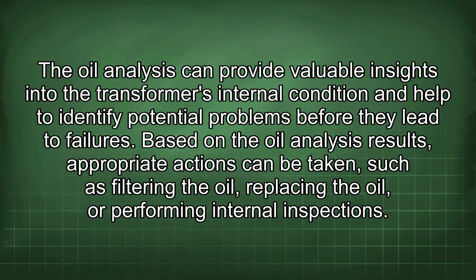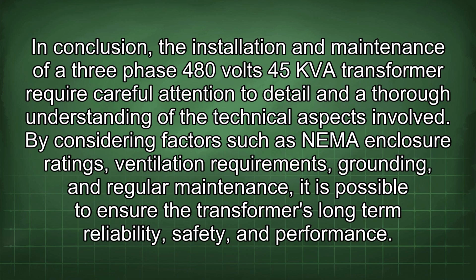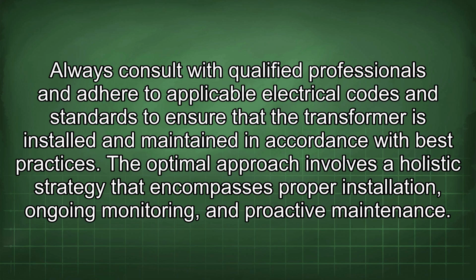performing internal inspections. In conclusion, the installation and maintenance of a three-phase 480 volts 45 kVA transformer require careful attention to detail and a thorough understanding of the technical aspects involved. By considering factors such as NEMA enclosure ratings, ventilation requirements, grounding, and regular maintenance, it is possible to ensure the transformer's long-term reliability, safety, and performance. Always consult with qualified professionals and adhere to applicable electrical codes and standards to ensure that the transformer is installed and maintained in accordance with best practices.